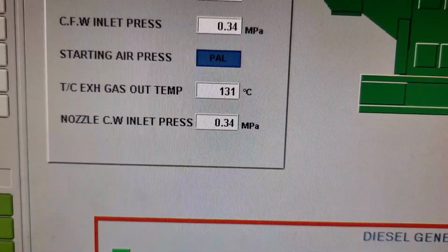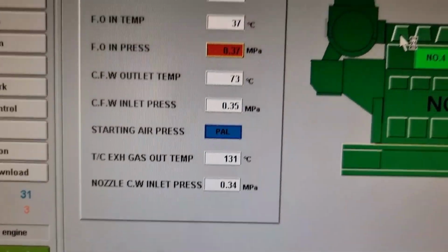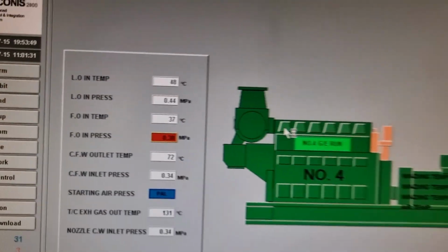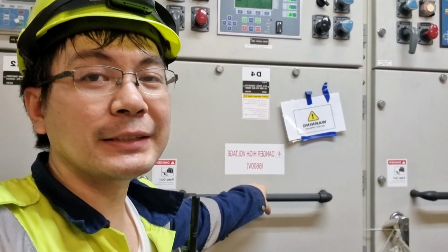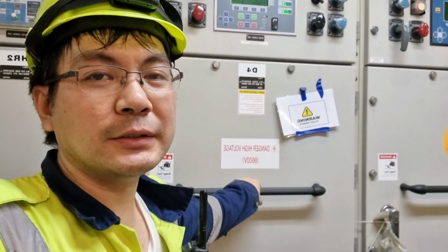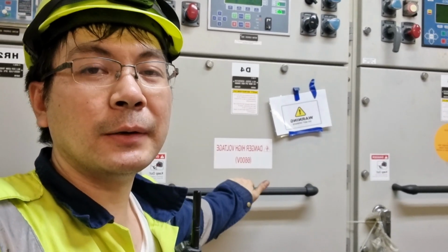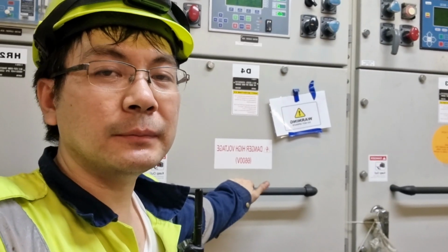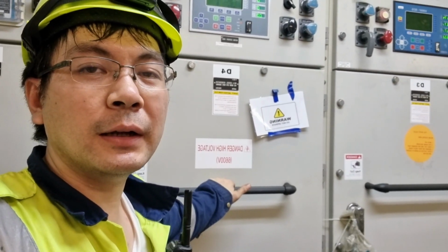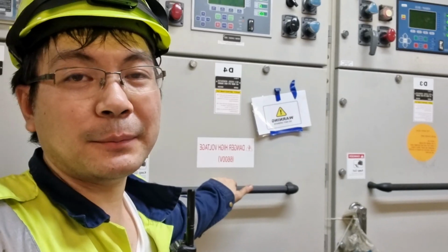And the readings started to build up, especially the one on the turbocharger. Now we have readings on our lube oil inlet pressure and our turbocharger outlet temperature sensor. They are not sensor fault anymore, but we found another problem.